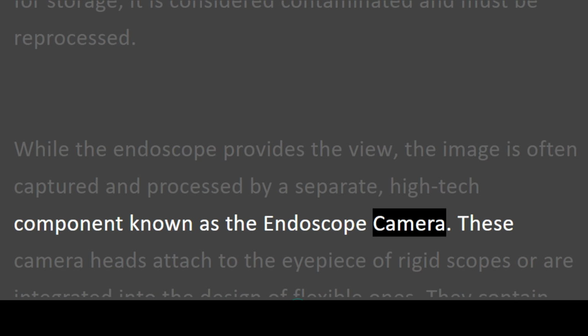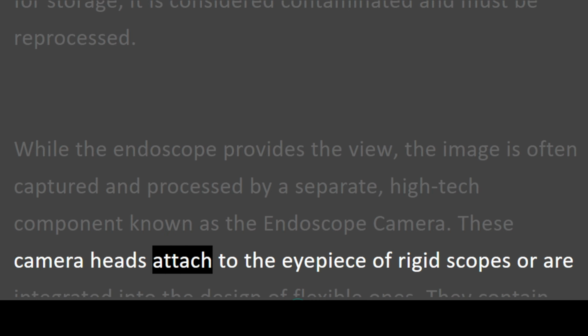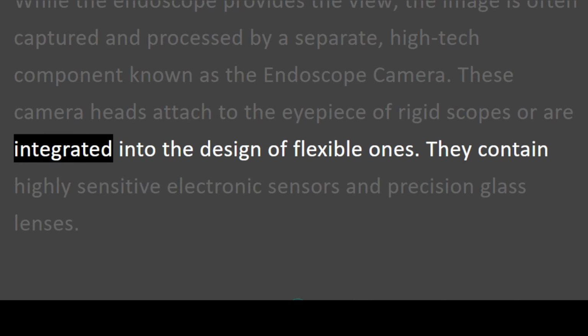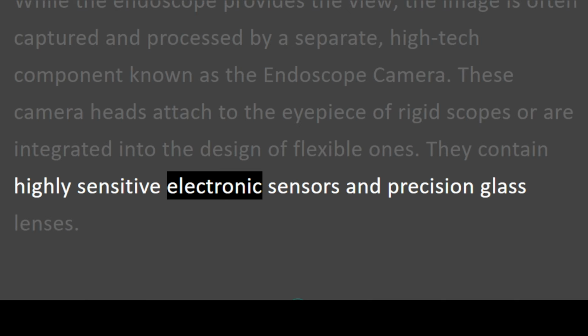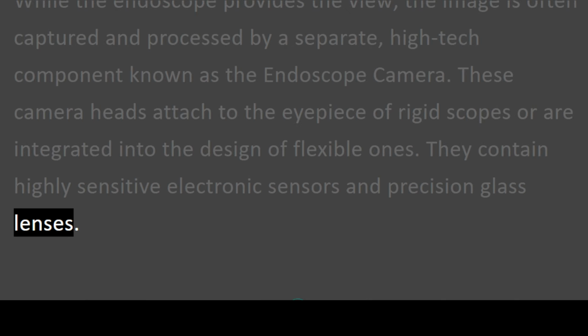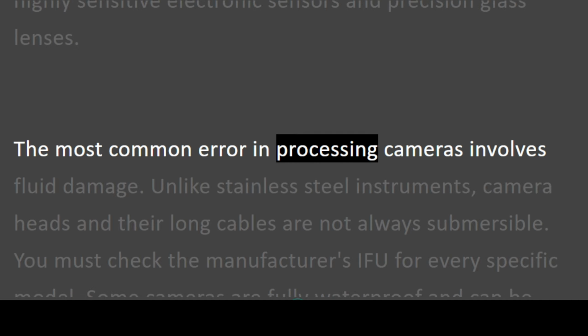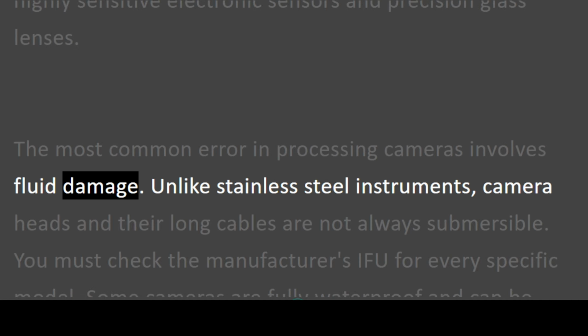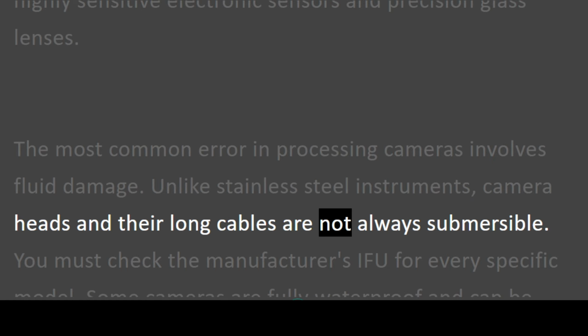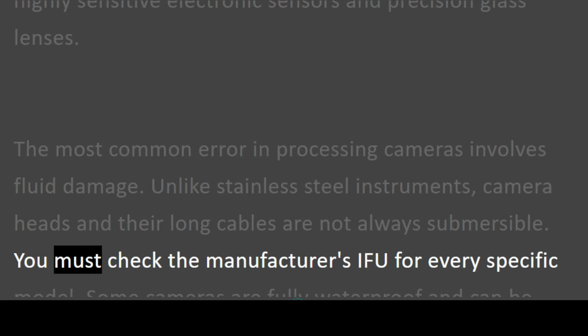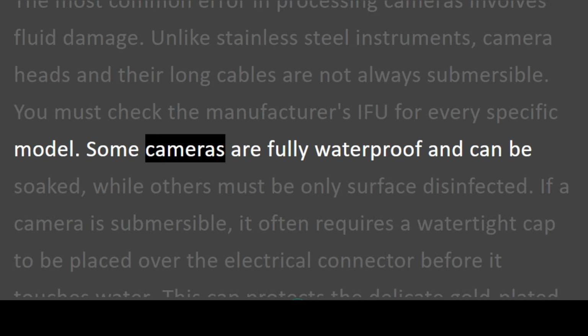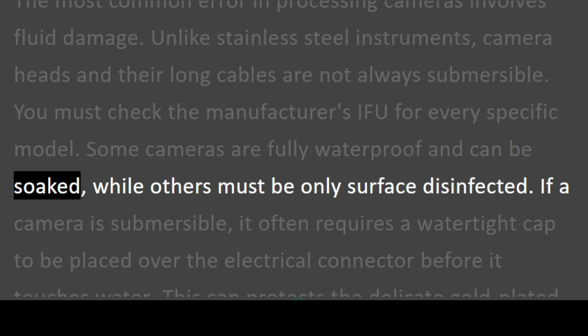While the endoscope provides the view, the image is often captured and processed by a separate, high-tech component known as the endoscope camera. These camera heads attach to the eyepiece of rigid scopes or are integrated into the design of flexible ones. They contain highly sensitive electronic sensors and precision glass lenses. The most common error in processing cameras involves fluid damage. Unlike stainless steel instruments, camera heads and their long cables are not always submersible. You must check the manufacturer's IFU for every specific model.